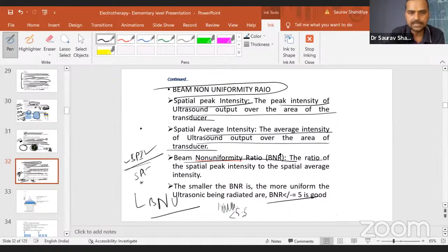I have shown the BNU ratio in the picture. You can see this is how intensity works in the transducer. This is the transducer head. I'm talking about this particular transducer head. All of you are able to see that. Here you have kept a gel, but this is not gel. Don't consider this gel. This is a pictorial presentation of the sound wave, where you can see the sound wave is as good as at a certain point and coming like this. So there is an average from the least wave it generates to the highest wave it generates. It's a summation, it's an average.